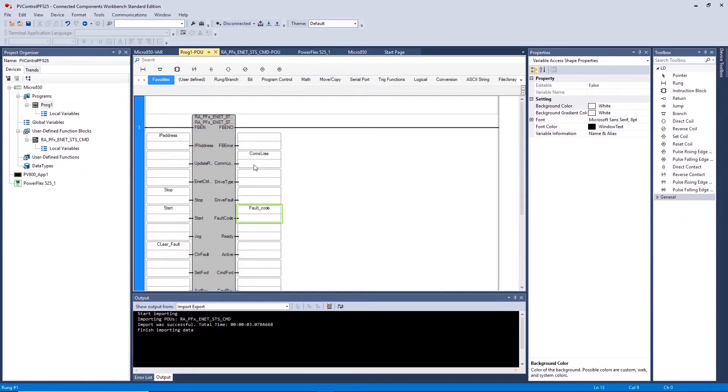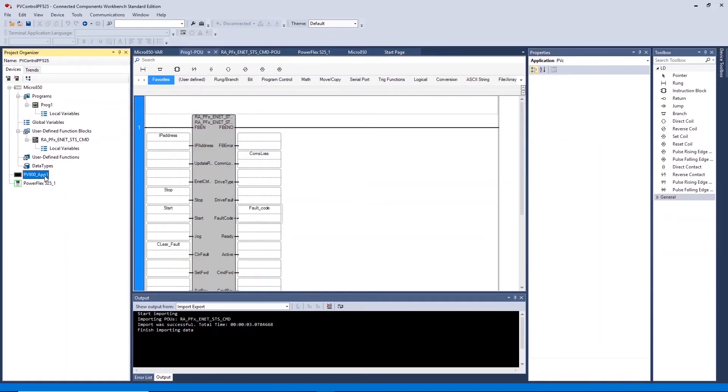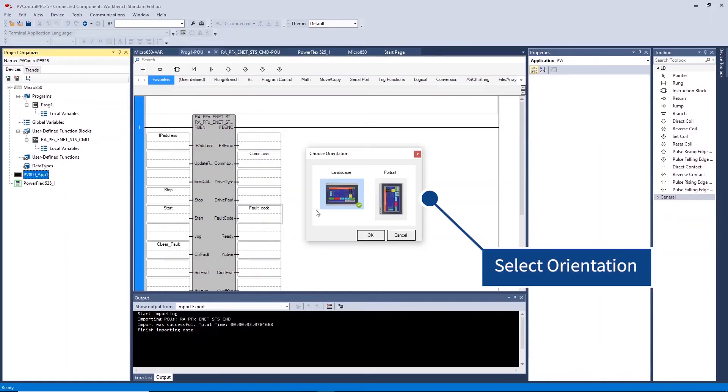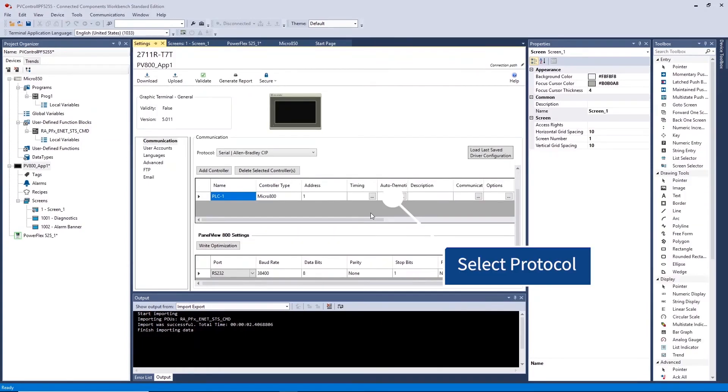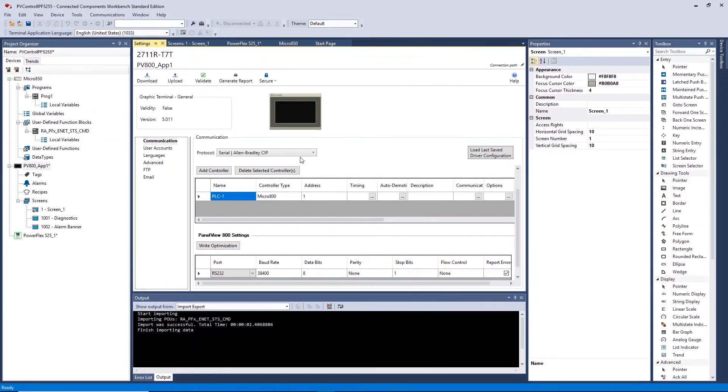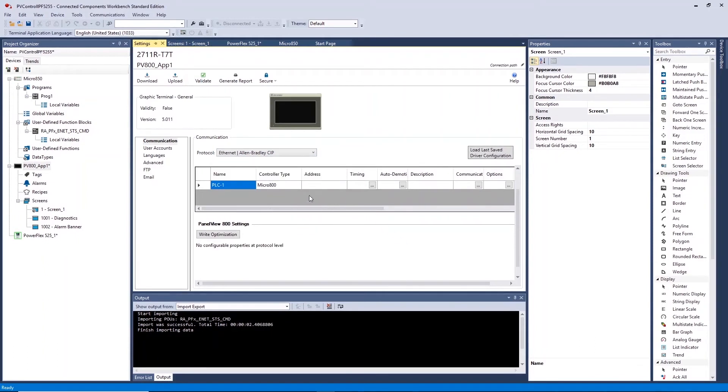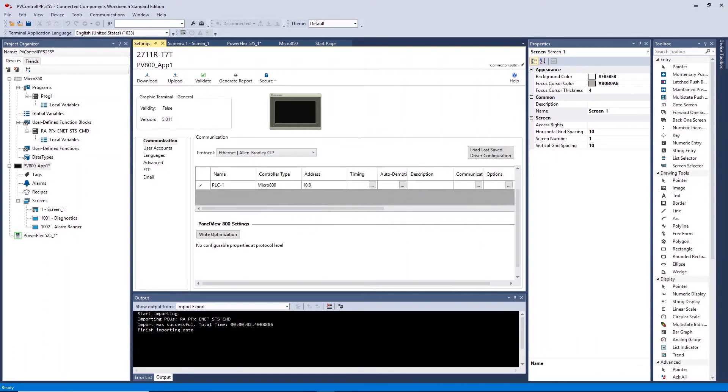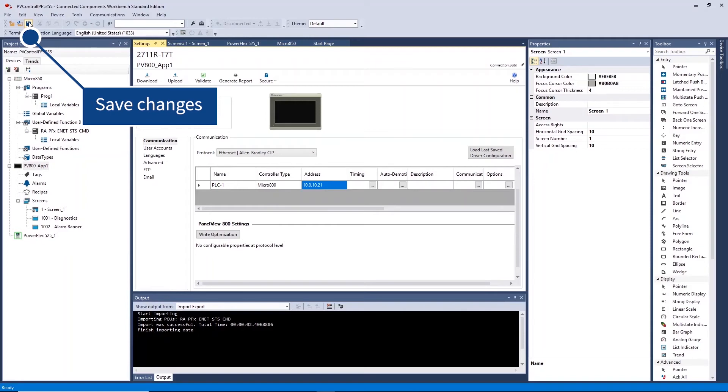Once complete open the HMI settings to configure and create the HMI application. First select the communications protocol to Allen Bradley Ethernet CIP. Now set the IP address of PLC1 to the IP address you have configured previously for your controller. Ensure you save the changes you have made.